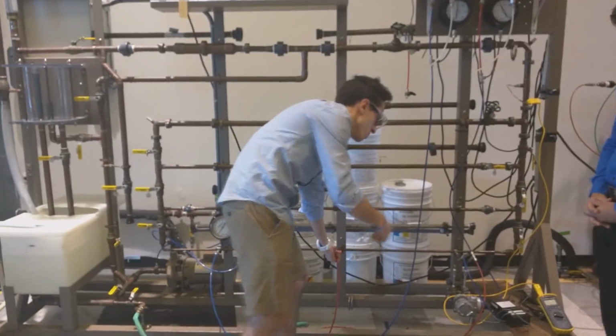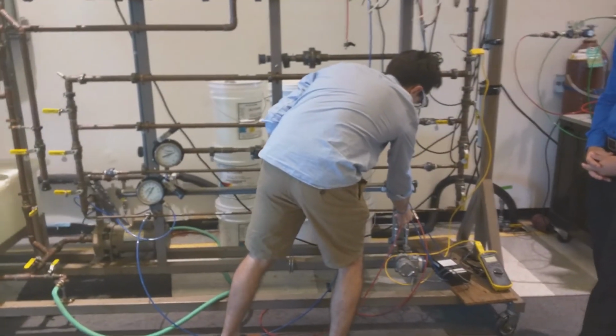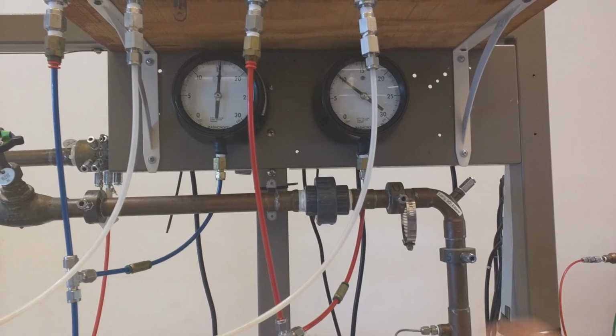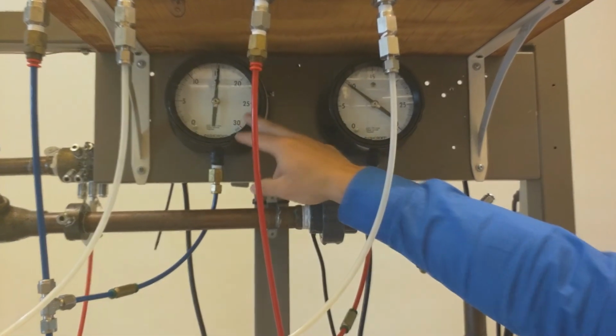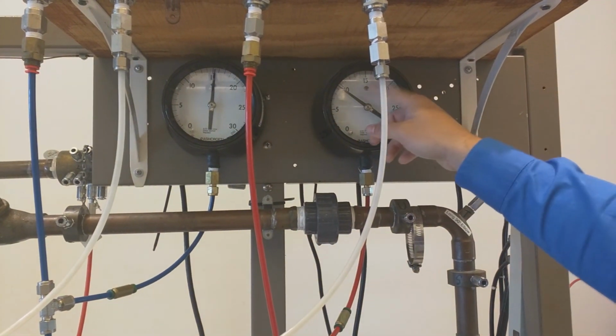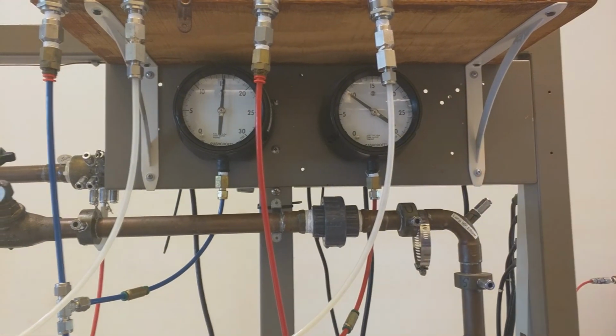And now you're going to take the probe from port 2 to port 3 and remeasure your pressure drop. As you can see, the pressure in 1 is the same, which it should be, but the pressure in 3 is less than the pressure in 2, seeing that there's a greater pressure drop.